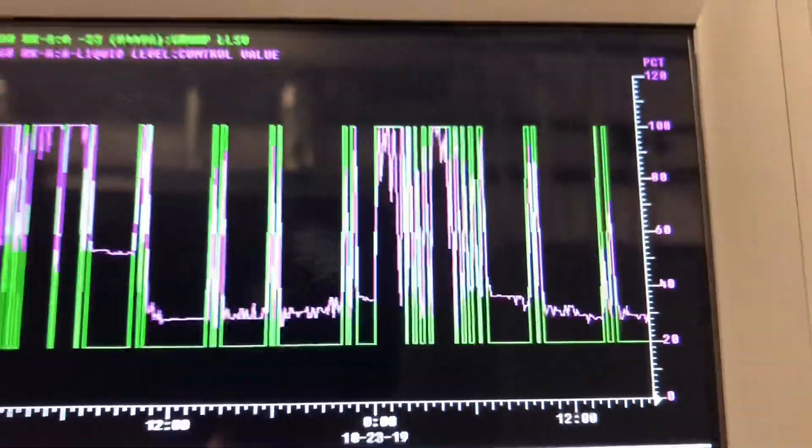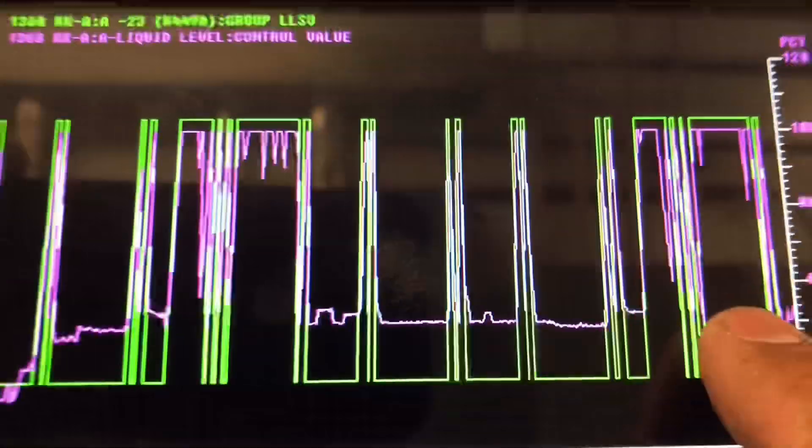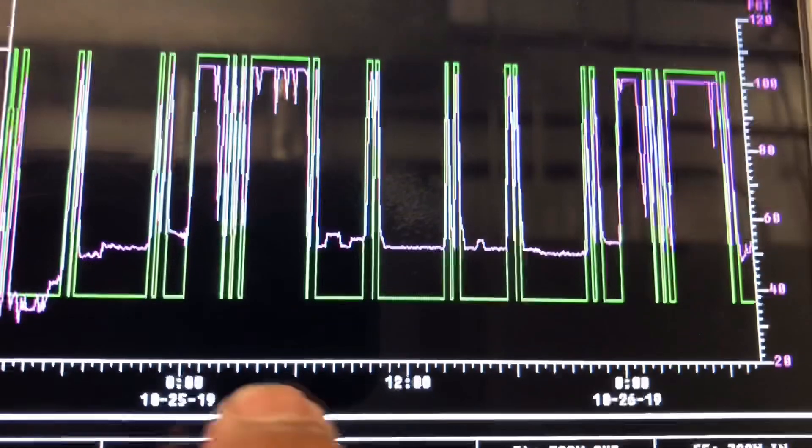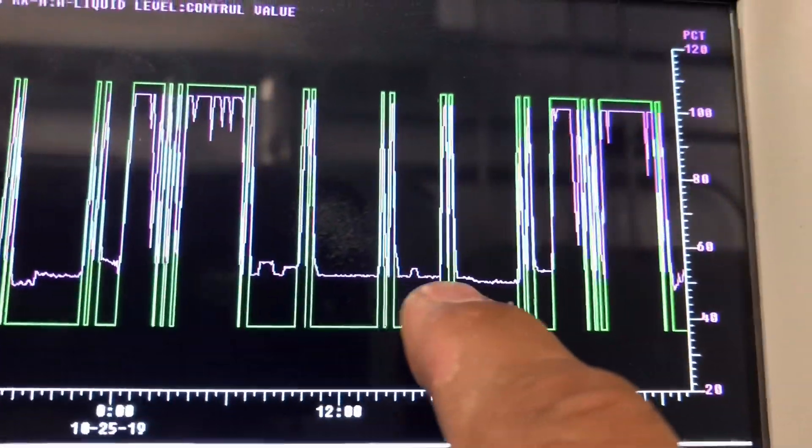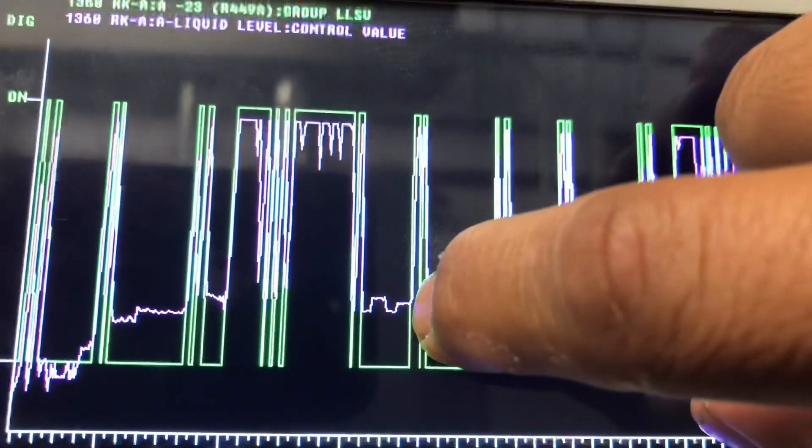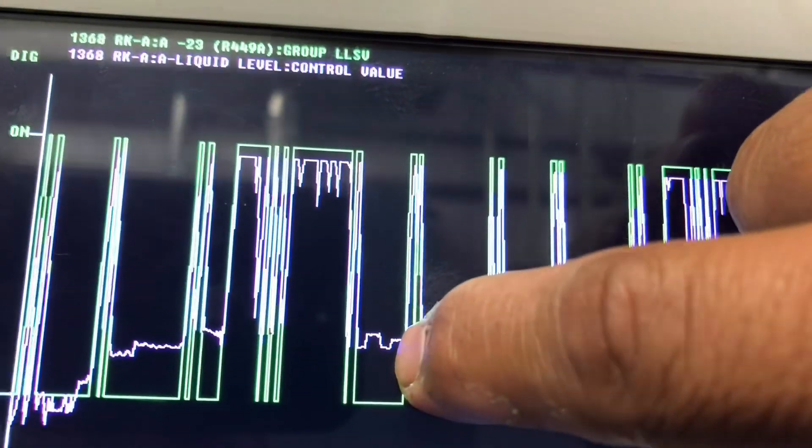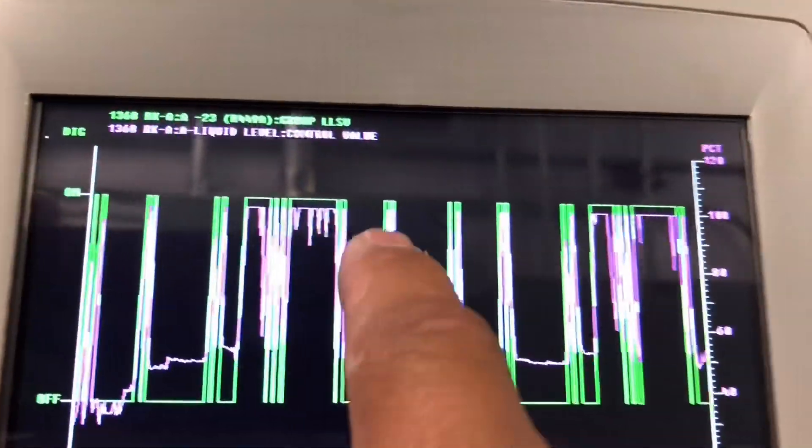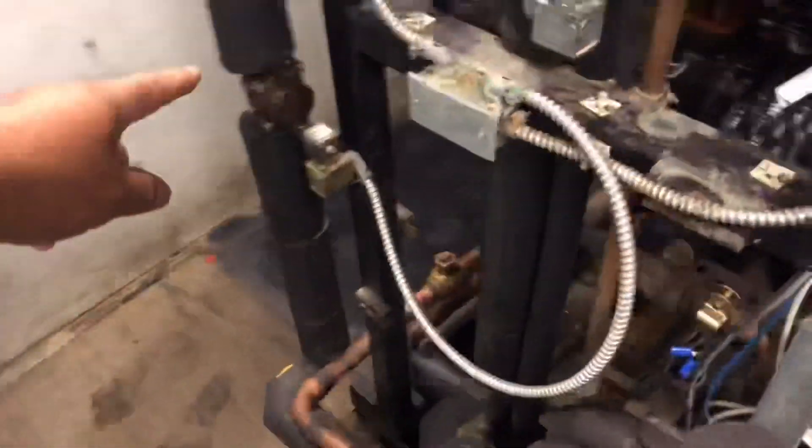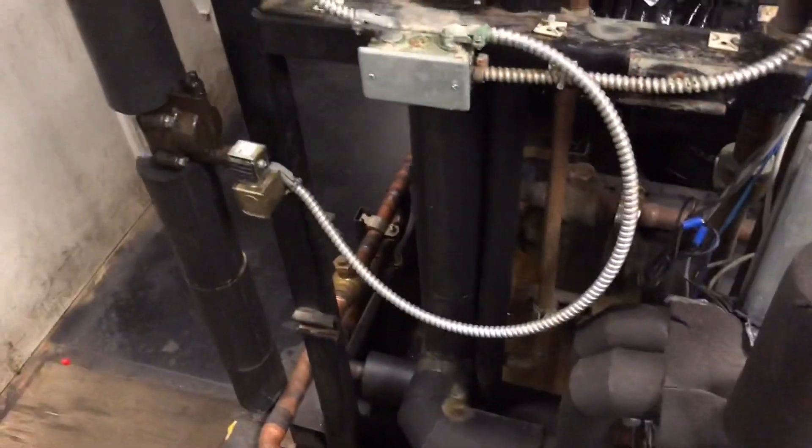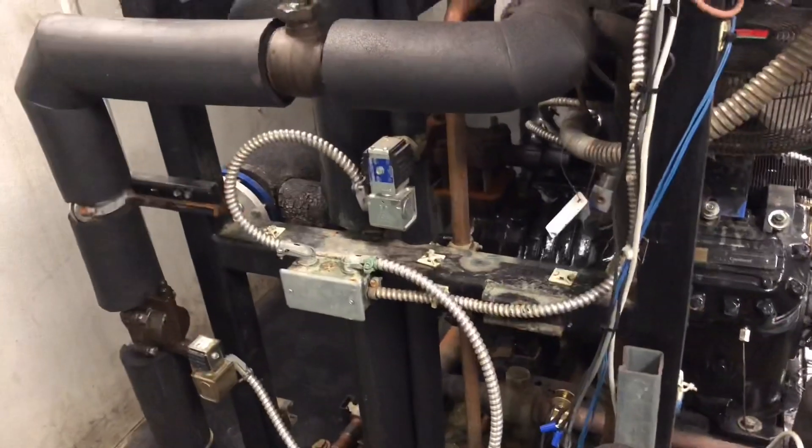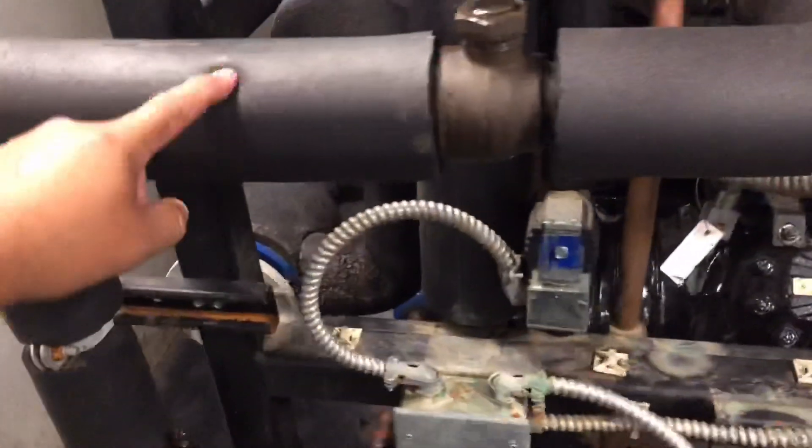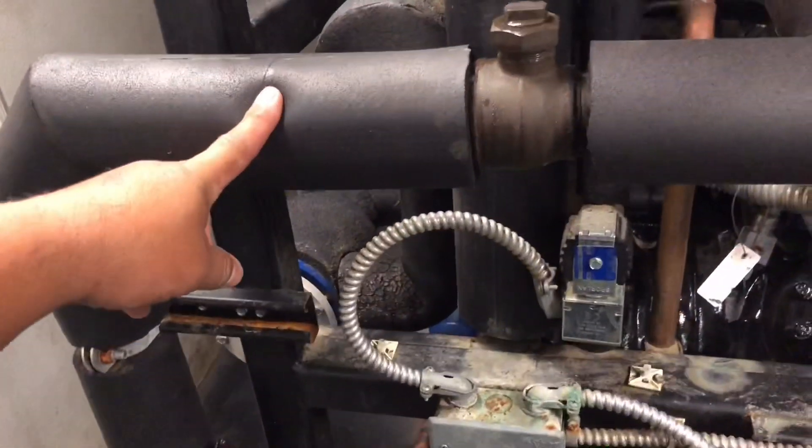Let's look at last night. Right here, see, it's not energized. Here during the day, it's not energized, my liquid level is fine. Once my OLDR valve energizes, my liquid level goes up. Pretty much, when that valve energizes, it holds back from the circuit. So when the cool gas goes to the cases and comes back as liquid, it can go back into the liquid line, if that makes any sense.